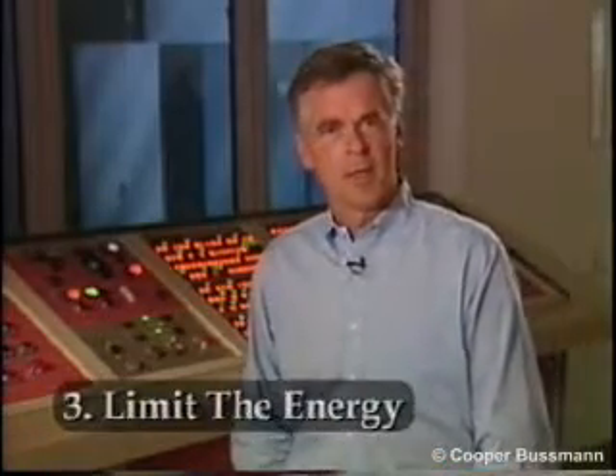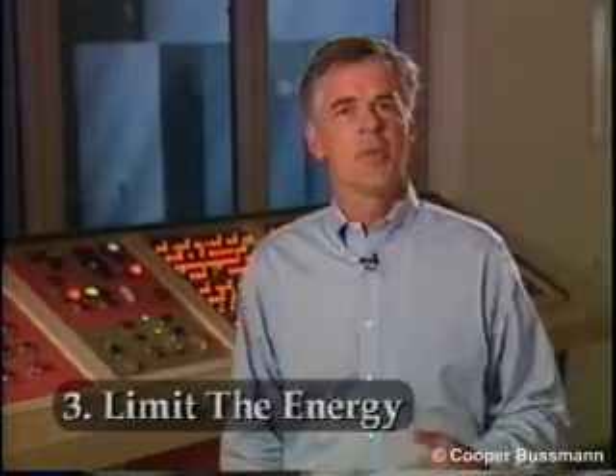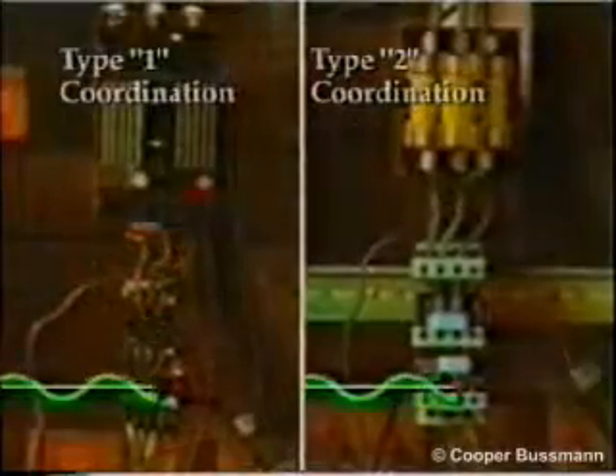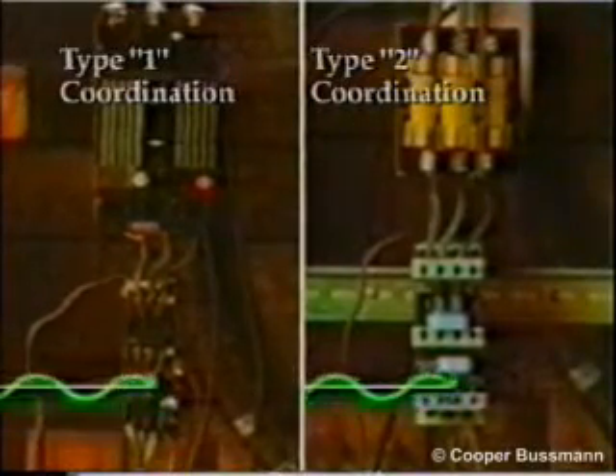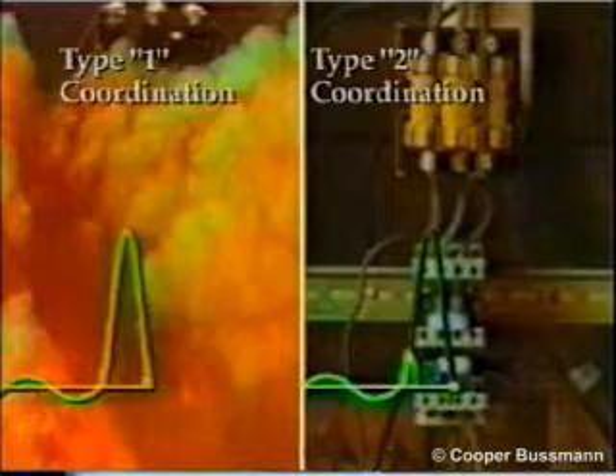Limit the energy. Circuits should also be designed to limit the available arc flash energy. The use of smaller or higher impedance transformers and current-limiting overcurrent protection devices will help to reduce the flash energy. This will provide improved protection for both equipment and employees. Many companies are going one step further by specifying Type 2 no-damage coordinated protection for motor starters. This not only reduces the damaging energy seen by the starter, but also helps to reduce the flash energy seen by employees.